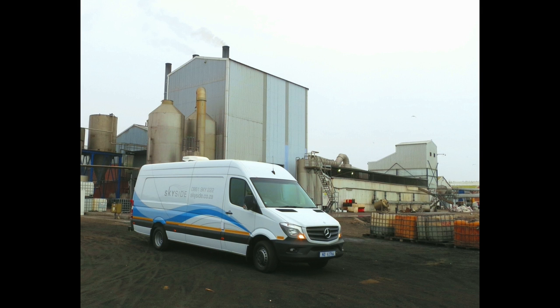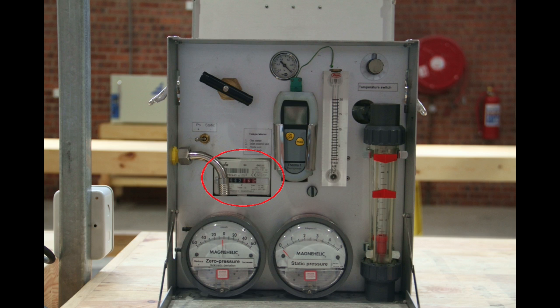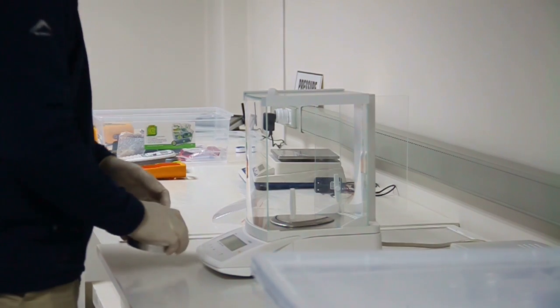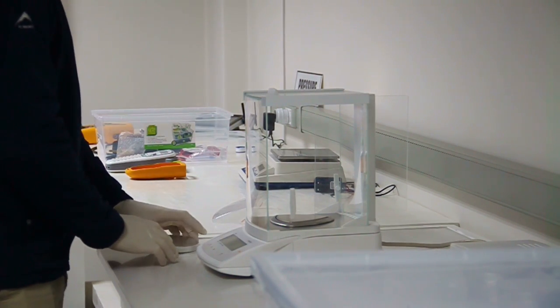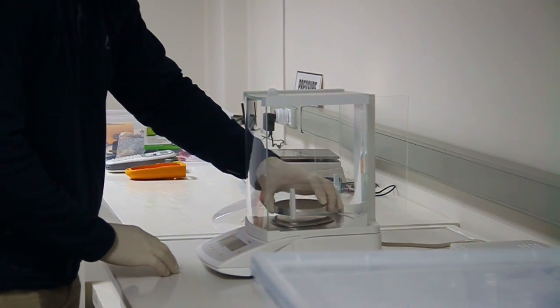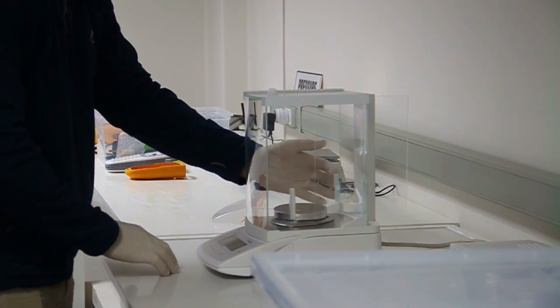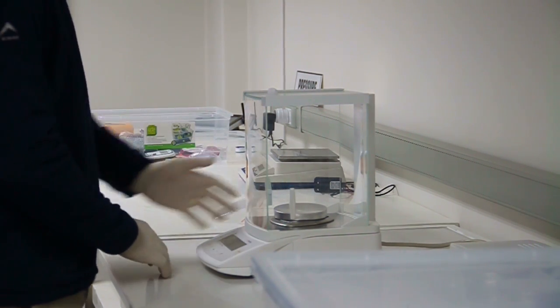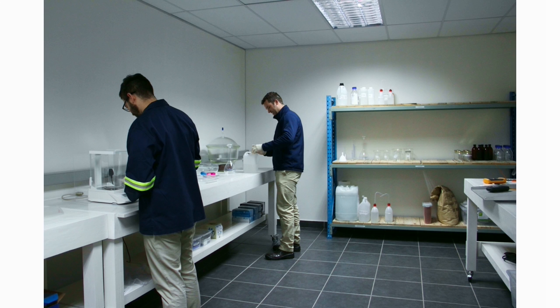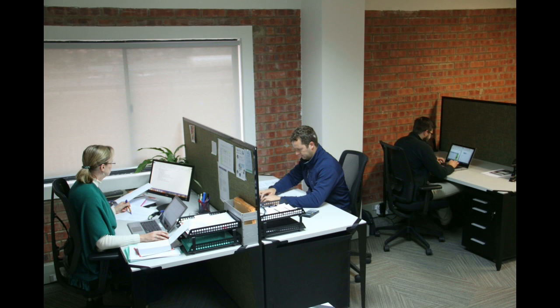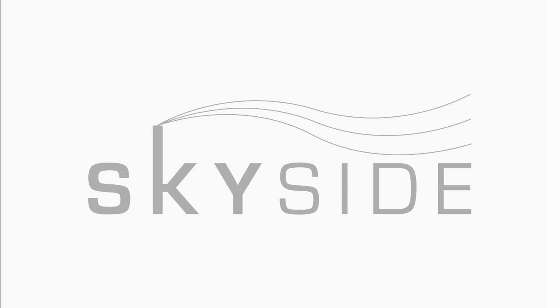The volume of the gas sample is known and is recorded and corrected to standard temperature and pressure. The mass of the dust sample is determined by drying and weighing the filter, both before and after sampling. The difference in weight gives us the mass of the dust that was collected. And the volume of the gas sample allows us to calculate the concentration of the dust being emitted by the source. And that concludes my simple breakdown.